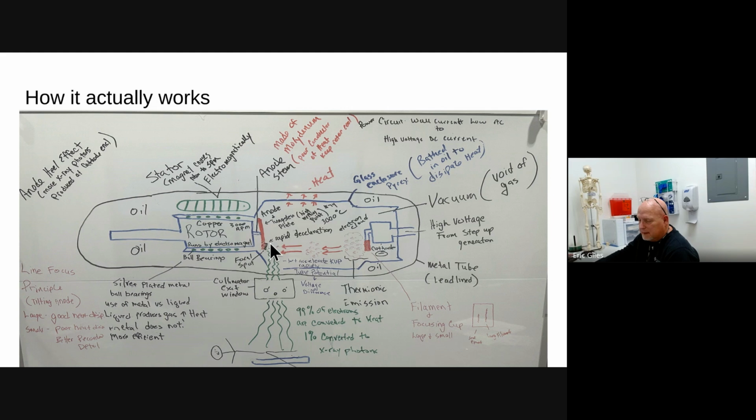And the reason they do that is if we shot X-rays all day long onto that tungsten plate right here, we would end up cracking or breaking that plate. So they decided that it's best that it be rotating, so it puts the heat on there equally and helps dissipate the heat a little bit better.